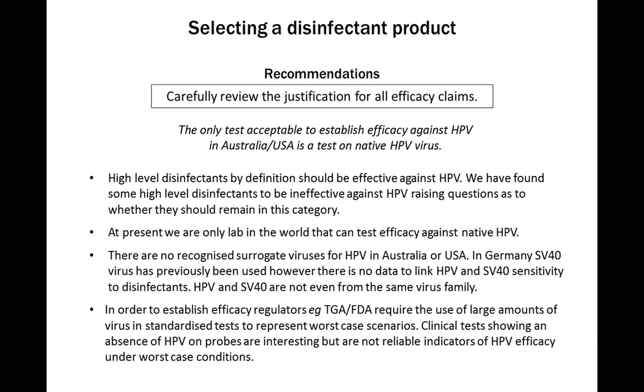Selecting a disinfectant product, our recommendations there would be to carefully review the justification for efficacy claims. The only test acceptable to establish efficacy against HPV in Australia or the USA is a test on native infectious HPV virus. High-level disinfectants, by definition, should be effective against HPV. We have found some high-level disinfectants to be ineffective against HPV, raising questions as to whether they should remain in this category. At present, we are the only lab in the world that can test efficacy against native HPV. There are no recognized surrogate viruses for HPV in Australia or the USA.